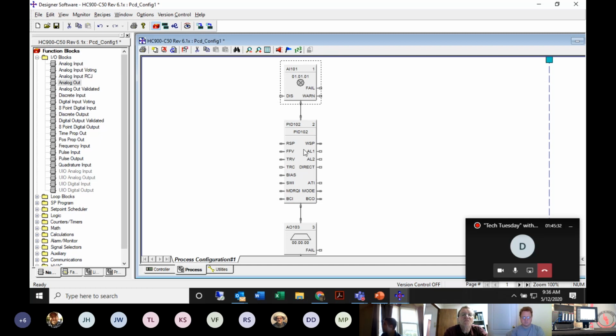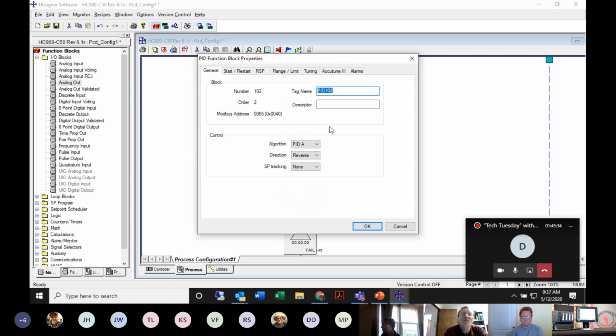Next, I've got to program my PID loop. If I double click on it, a lot of the terminology at the top will mimic what you see in a UDC. On the general tab, I have to give it a name. So let's say it's zone 1. If you remember in the UDC class, we talked about different algorithms: PIDA, PIDB, duplex. This is where you choose your algorithm. We talked about reverse and direct acting. Reverse is always for heating, direct is always for cooling. In this application, we have a reverse acting.